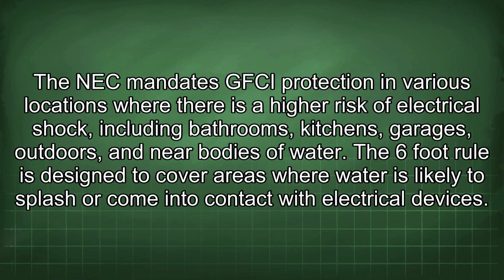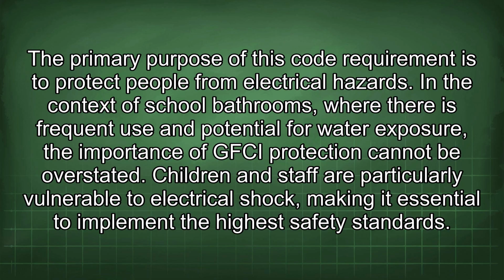The NEC mandates GFCI protection in various locations where there is a higher risk of electrical shock, including bathrooms, kitchens, garages, outdoors, and near bodies of water. The 6-foot rule is designed to cover areas where water is likely to splash or come into contact with electrical devices. The primary purpose of this code requirement is to protect people from electrical hazards. In the context of school bathrooms, where there is frequent use and potential for water exposure, the importance of GFCI protection cannot be overstated. Children and staff are particularly vulnerable to electrical shock, making it essential to implement the highest safety standards.